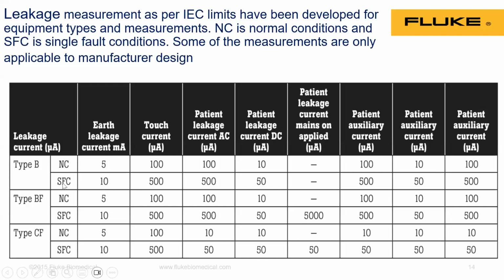Now when there is a single fault condition, and the machine is not tripping and is still working, ideally it could have stopped. In the single fault condition, the current goes higher, but how much higher it may go is also defined in the standards. Suppose the machine is in single fault condition, the earth leakage current should not be more than 10 milliamperes. Even patient leakage, if it is DC, should not be more than 50 microamperes. As you have seen, AC currents are more, so DC currents are generally less. For every type of equipment, type B, type BF, type CF, IEC has clearly given the recommendations, for both the normal condition and the single fault conditions.